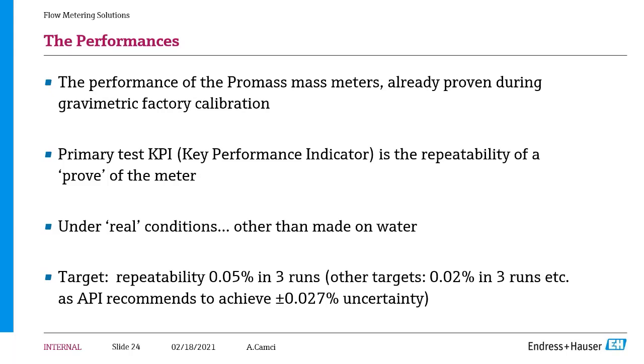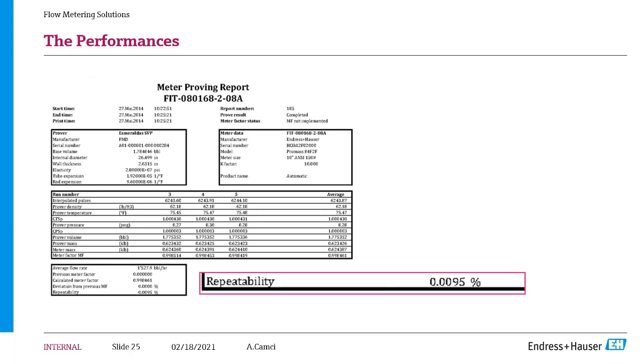What does better mean? I will show you a proving report. This is a real proving report made by the small volume piston prover and the Coriolis meter. As you can see here, while the repeatability requirement is 0.05%, we reach a repeatability of 0.0095. This is an excellent result and shows the performance of the Endress+Hauser Coriolis meter.